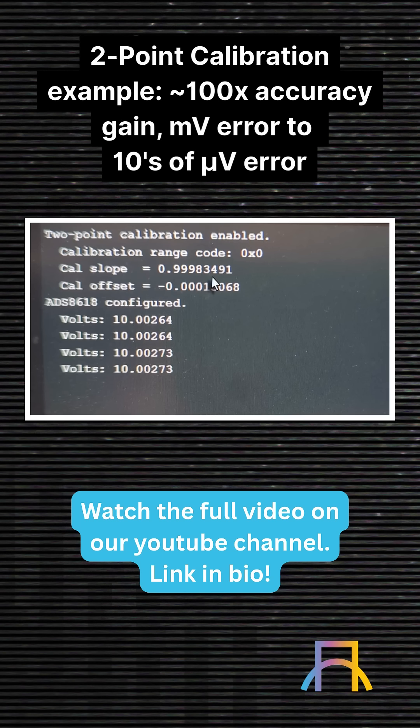We can see the slope is less than 1. So that must mean the error slope is greater than 1. Our correction factor is pulling it less than 1 to make it 1. And then our offset error is actually positive, so our correction factor is negative.